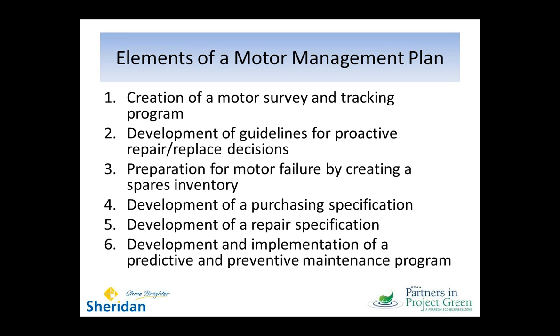And I've pulled up a bit of a case study here, which is the Reedy Creek Improvement District, which sends chilled water out to Walt Disney World facilities and has about 20,000 horsepower worth of motors. And so they used a DOE software tool to do the motor survey and track and identify what motors were in place. And so they pulled up a survey of about 120 motors at the North Service Area chiller plant. These motors ranged from 25 to 700 horsepower. And primarily these were about water pumping, so chilled water, condenser water, municipal water, and some of the compressor and cooling tower motors.